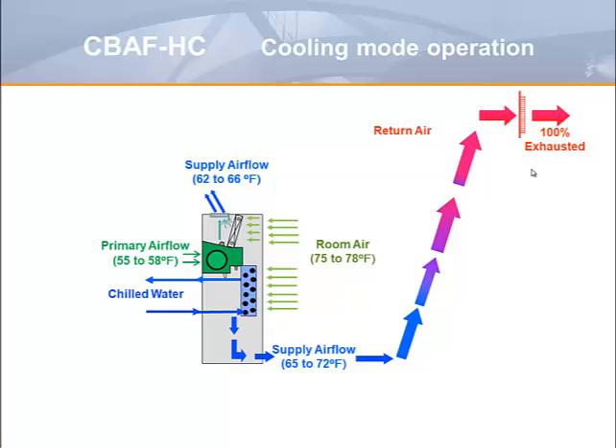This slide illustrates the operation of the unit in the cooling mode. Primary air is delivered through the induction nozzles. The velocity of the nozzles induces room air through the integral heat transfer coil, which is then cooled in accordance with the space thermostat demands prior to mixing with the primary air. The use of room air induction and reconditioning allows the use of 100% outdoor air as a primary air source.